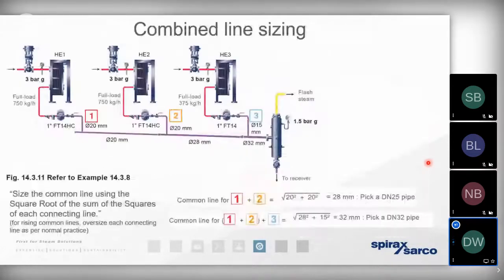So it is acceptable to bring multiple condensate lines together from multiple processors. The only thing we need to bear in mind is that processes can be discharging condensate at different mass flow rates, different pressures, different temperatures. So where those lines converge, they need to step up accordingly to allow for the appropriate mass and volume of the liquid condensate, but also of the volume of flash steam as a result of any phase change there may be. Don't get confused by this little formula that's demonstrated at the bottom of the screen, because of course you can use those calculators and configurators to help you do that.